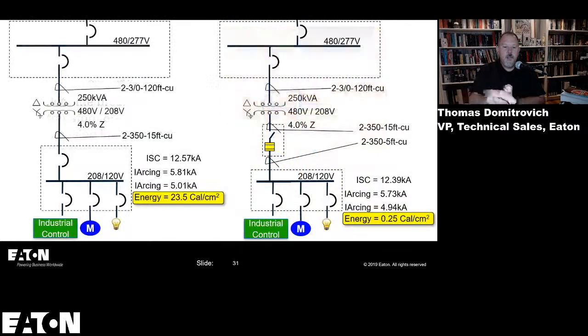So imagine taking this breaker, this overcurrent device, out of that panel board and then integrating it with the transformer. You kill a couple birds with one stone. You don't have an extra enclosure that you have to install. Normally these panel boards are pretty doggone close to that transformer. I don't know if you've ever seen those. Sometimes you'll see the primary panel, the transformer, and the secondary panel, because there are some requirements on the length of those leads, the secondary transformer conductors. So this solution provides the ability to reduce the incident energy considerably in a panel board that is more likely to be entered to do justified energized work or maintenance or things of that nature.